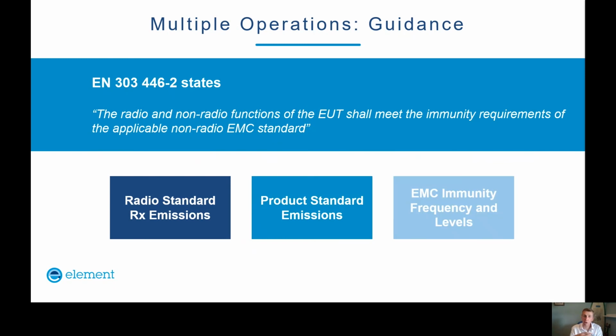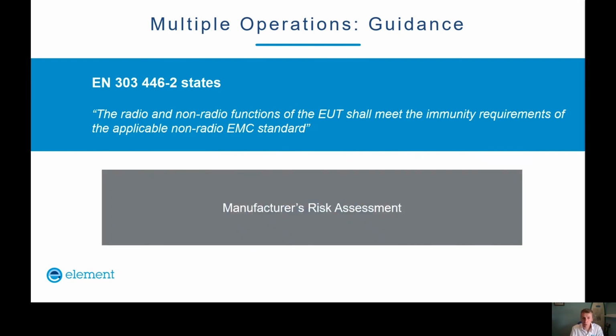Also, with EMC immunity testing, being radio equipment, the frequency range of testing would be wider, such as radiated immunity testing from 80 megahertz to 6 gigahertz, whereas the EMC standard may not have called for that. Meanwhile, the EMC standard, say from a medical or industrial environment, would have much higher levels, such as 10 volts per meter. So with your combined product, you end up doing a wide frequency range and a high immunity level. This all needs to be documented in the risk assessment, and it's a topic in progress regarding the application of spurious emissions limits.